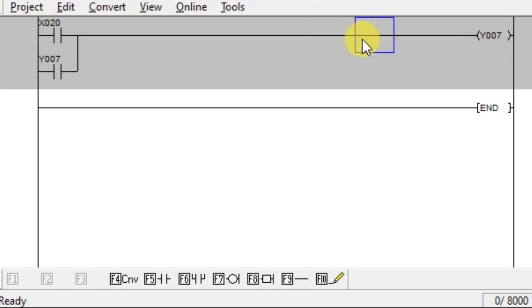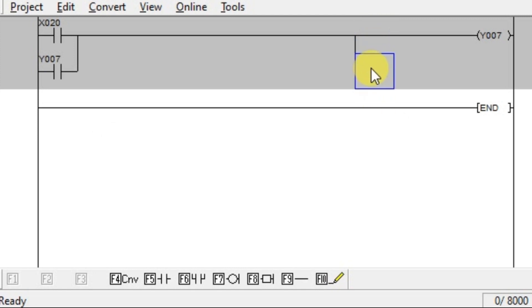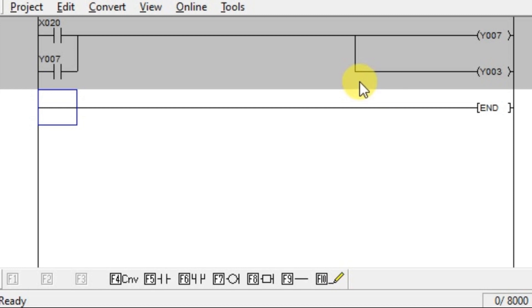We have to activate the buzzer also. Take one vertical line, select there, take one output coil, and enter the address of the buzzer, which is y3. Next, we have to turn off these two outputs — yellow lamp and buzzer — after 10 seconds. So we need a timer to unlatch both outputs y7 and y3 after 10 seconds. Select there, enter a vertical line, then take one output coil instruction and enter a timer: T0, K100 for 10 seconds. If you need 5 seconds, enter 50.